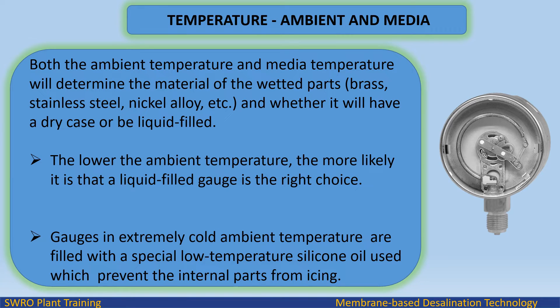Temperature — ambient and media: Both the ambient temperature and media temperature determine the material of the wetted parts (brass, stainless steel, nickel alloy, etc.) and whether the gauge will have a dry case or be liquid filled. The lower the ambient temperature, the more likely a liquid filled gauge is the right choice. Gauges in extremely cold ambient temperatures are filled with a special low-temperature silicone oil to prevent internal parts from icing.